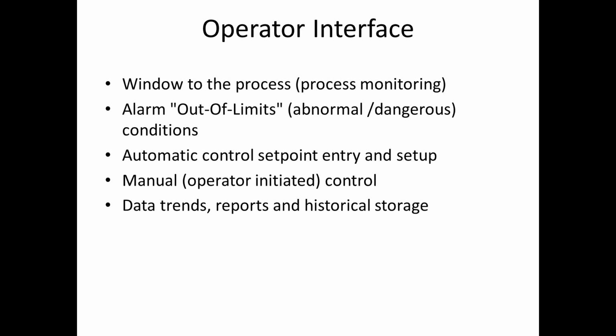The operator interface would allow you to control the set point. Like I said, the set point in the aeration basin may be 1.5 parts per million, but maybe for some reason you wanted to have a higher level of dissolved oxygen in the plant. It's a very simple process through the operator interface system to just change that set point entry. And like I said, manual control allows you to take control of pieces of equipment for something that is not a normal configuration, taking pieces of equipment offline, or maybe bringing a piece of equipment online. Sometimes it's more helpful to have an operator do a startup in manual and then turn the process over into automatic.